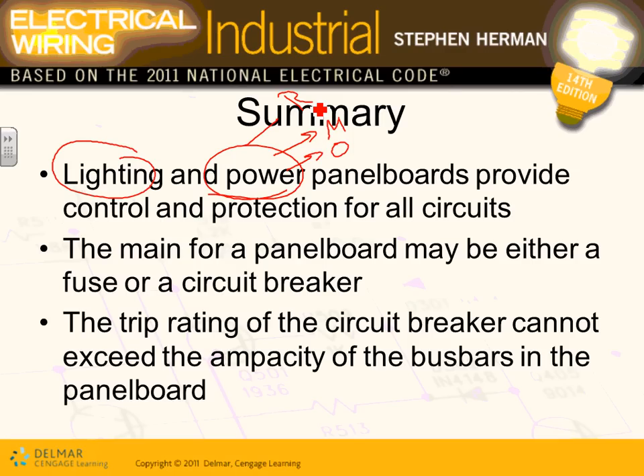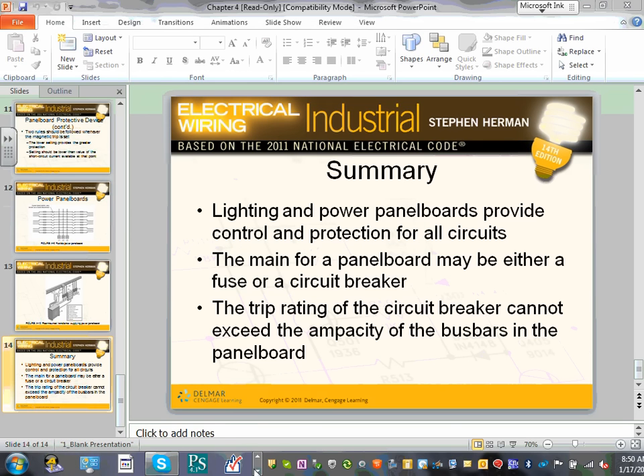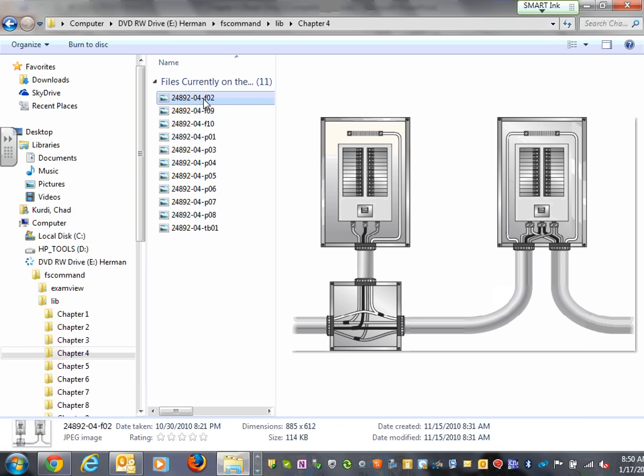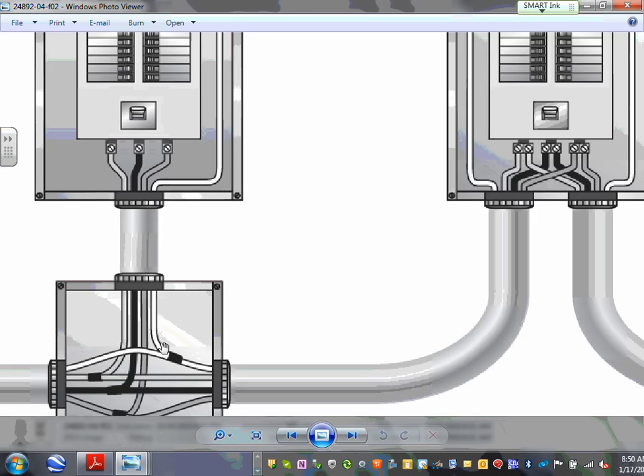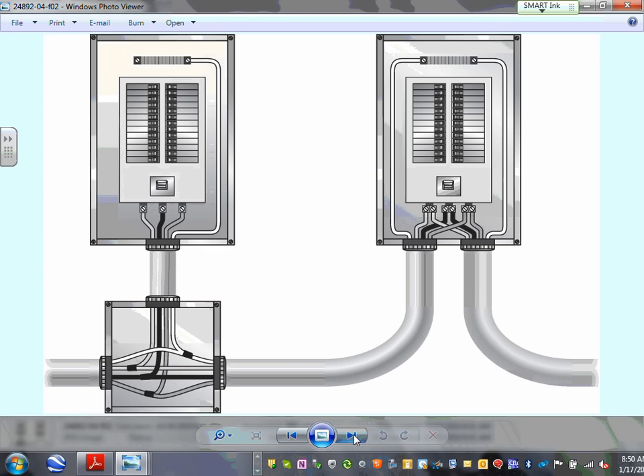You can have a circuit breaker panel or a fuse disconnect panel. The trip rating of a circuit breaker cannot exceed the capacity of the bus bar. Like we said, if your bus bars are rated for 225 amp, you have to have a 225 amp circuit breaker or less. So that's all I'm going to show you. Let me just take one second to show you one other thing. So panels, guys, we talked about panels many times. So here's how they tap them. Very interesting. Save some money.